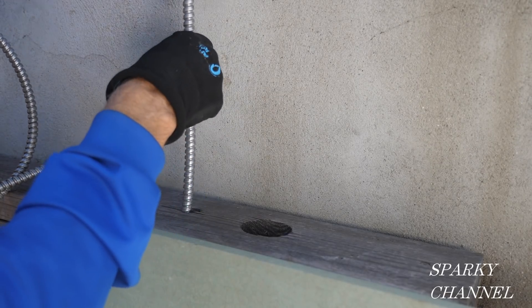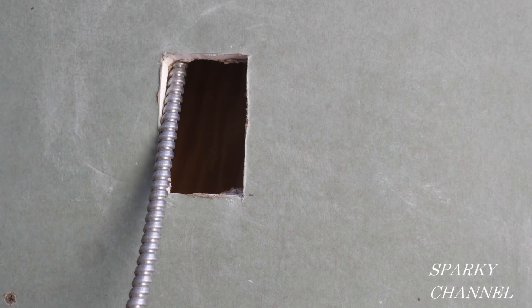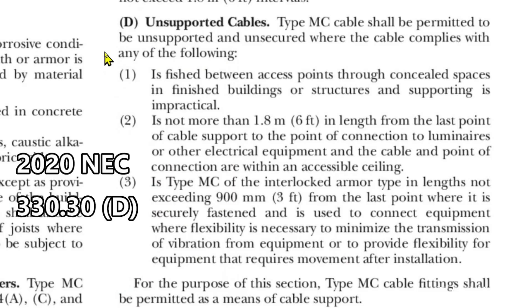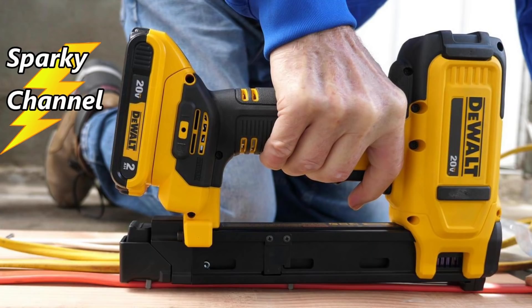With the MC cable you get six feet, so that's one advantage to using MC cable in this kind of situation. Another important consideration: when you fish cable behind a wall — perhaps for seven feet — if you fish it with MC cable you're giving yourself more protection from screws and nails and so forth that might be sticking out of the drywall. If you use MC cable you're protected to a greater degree from situations like that. I'll put links in my video description for this spiral-bound NEC code book and for the NEC 2020 handbook, also links for Ugly's reference books and for the DeWalt cable stapler. Thanks, I hope this video was helpful.